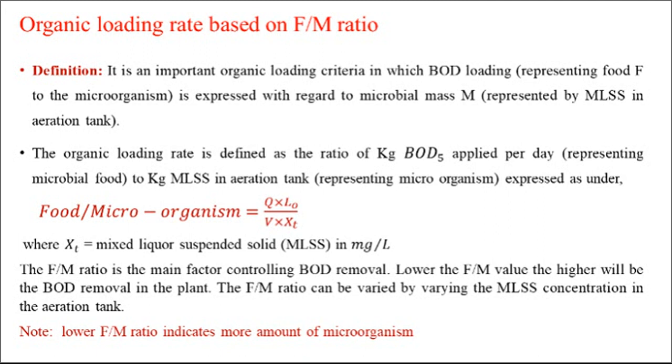This organic loading rate is defined as the ratio of kg BOD applied per day, representing microbial food, to the kg MLSS in the aeration tank, or F/M ratio is equal to Q into L0 divided by V into XT, where Q into L0 is the food coming to the aeration tank, and V into XT is the microorganisms in the aeration tank in a particular volume.